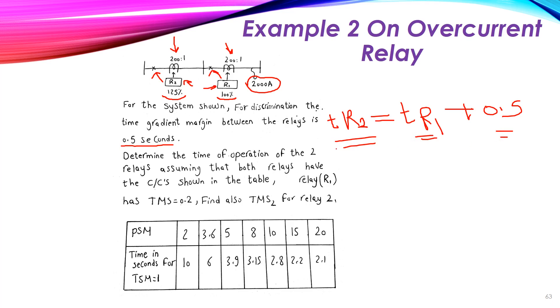So R2 = R1 + 0.5 seconds. What is required? Determine the time of operation of the two relays, assuming that both relays have the characteristics shown in the table. You can see here the plug setting multiplier values and the time in seconds at TSM equal to 1. We need first the time of both relays.